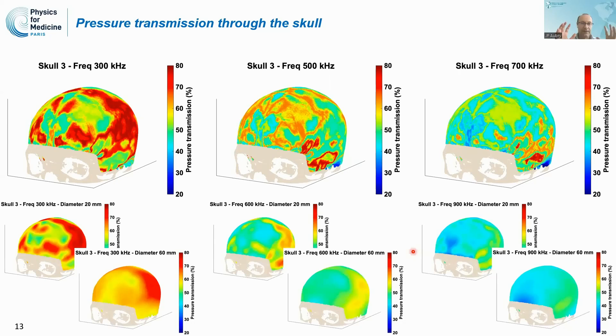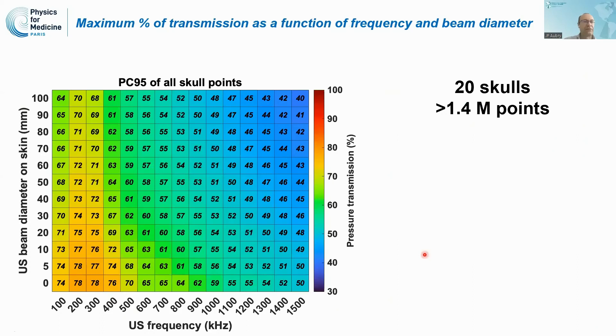Depending on where the transducer is located, transmission will be higher or lower. For all those configurations, we determined the 95th percentile in order to find the maximum transmission realistically transmitted through the skull for a given frequency and ultrasound beam diameter on the skull surface. We did this on 20 skulls, considering more than 1.4 million points, and these are the transmissions obtained.